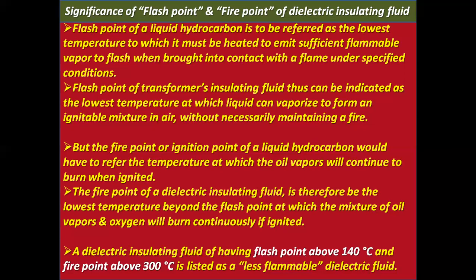But the fire point or ignition point of a liquid hydrocarbon refers to the temperature at which the oil vapors will continue to burn when ignited. The fire point of a dielectric insulating fluid is therefore the lowest temperature beyond the flash point at which the mixture of oil vapors and oxygen will burn continuously if ignited.